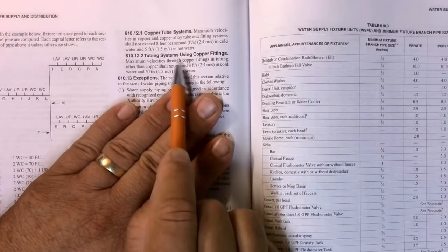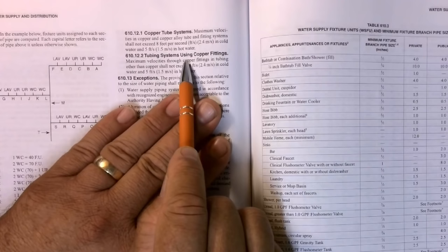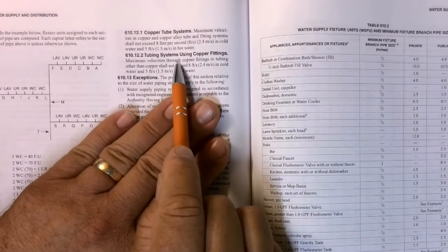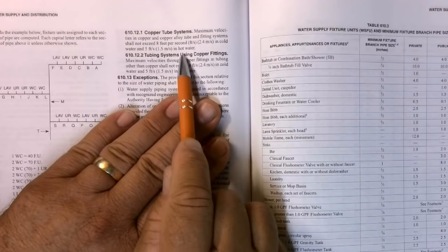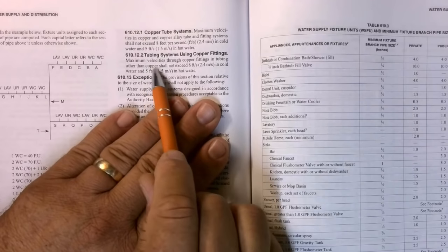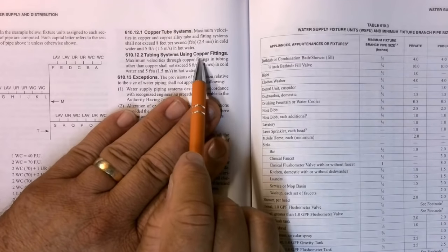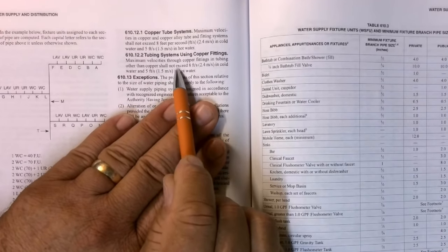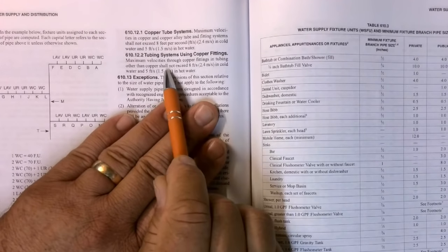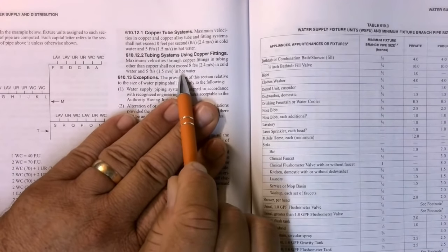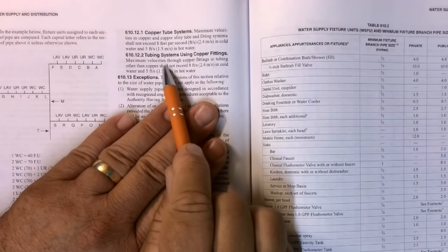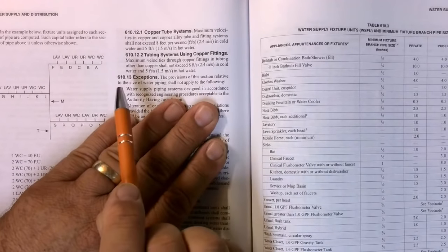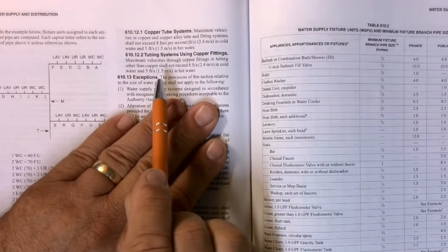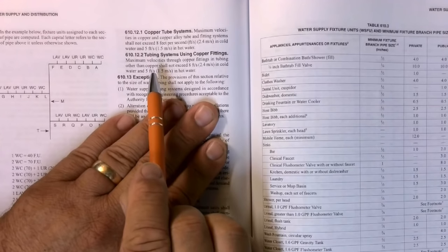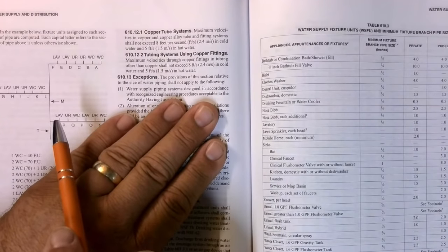8 feet per second. Tubing systems using copper fittings. Maximum velocity through copper fittings, okay? Copper fittings in tubing other than copper shall not exceed 8 feet per second in cold and 5 feet per second in hot. So it doesn't matter what type, anything using copper fittings, 8 feet per second in cold, 5 feet per second in hot.